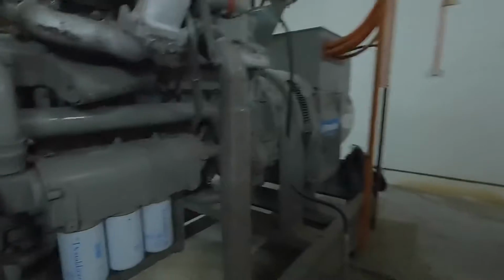Okay, I'm now at Ritz Carlton Residences Genset room. We're going to test run this genset using the same method remotely from the ATS panel. Okay, I'm going to jump the signal to allow the genset to start automatically, and release the jumper wire and allow it to stop automatically. Okay, same as usual, I'm going to check the parameters visually before we test run the genset. Let's check any leakages of oil. No leakages of oil. Engine oil, any leakages? No oil leakages. Radiator water, no radiator water leakages.